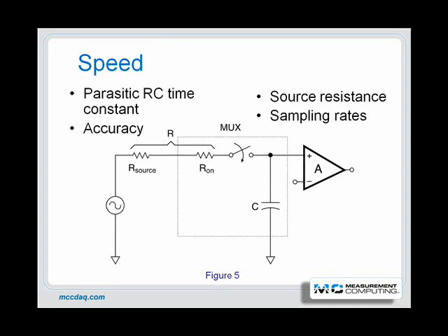Multiplexing reduces the rate at which data can be acquired from an individual channel because of the time-sharing strategy between channels. For example, an ADC that can sample a single channel at 100 kilohertz is limited to a 12.5 kilohertz per channel sampling rate when measuring 8 channels. Additionally, the multiplexer's high source impedance can combine with stray capacitance to increase settling time and generate crosstalk. A solid-state multiplexer with an impedance of tens or hundreds of ohms is worse than a relay with a typical resistance of 10 milli-ohms or less.